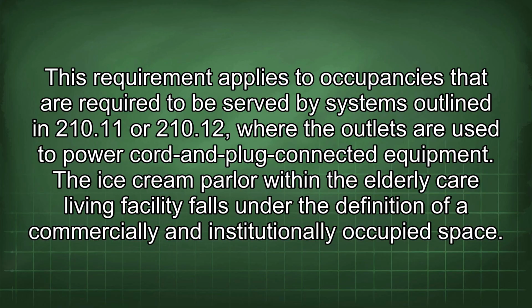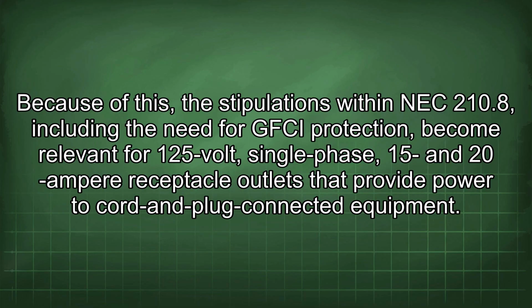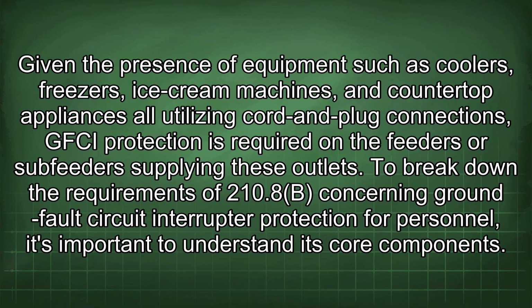The ice cream parlor within the elderly care living facility falls under the definition of a commercially and institutionally occupied space. Because of this, the stipulations within NEC 210.8, including the need for GFCI protection, become relevant for 125-volt single-phase 15 and 20 ampere receptacle outlets that provide power to cord and plug connected equipment. Given the presence of equipment such as coolers, freezers, ice cream machines, and countertop appliances all utilizing cord and plug connections, GFCI protection is required on the feeders or subfeeders supplying these outlets.